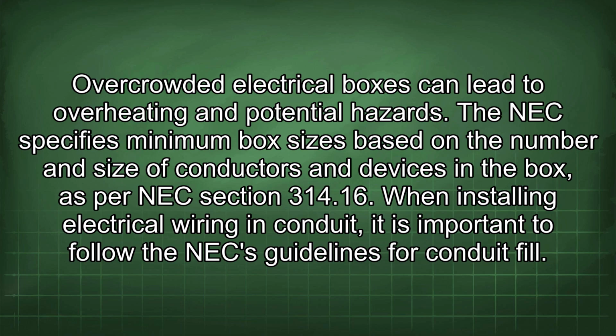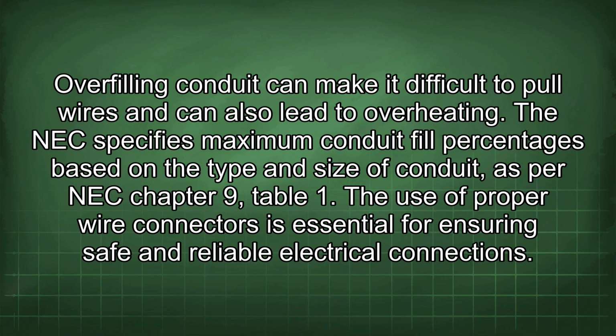When installing electrical wiring in conduit, it is important to follow the NEC guidelines for conduit fill. Overfilling conduit can make it difficult to pull wires and can also lead to overheating. The NEC specifies maximum conduit fill percentages based on the type and size of conduit, as per NEC Chapter 9, Table 1.